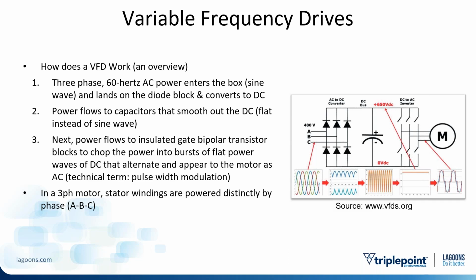And then the third step is flowing over to the IGBTs, the insulated gate bipolar transistor blocks, and they chop the power into bursts of flat power as opposed to that sine wave. Those bursts of flat power of direct current actually alternate. That's how the drive is putting this out. They alternate, and they then appear to the motor as if they were alternating current. A technical term for that is pulse width modulation.